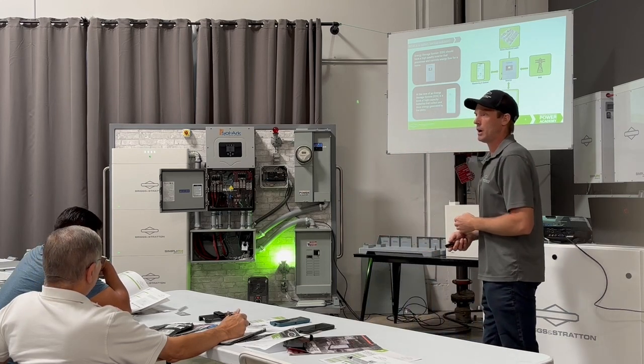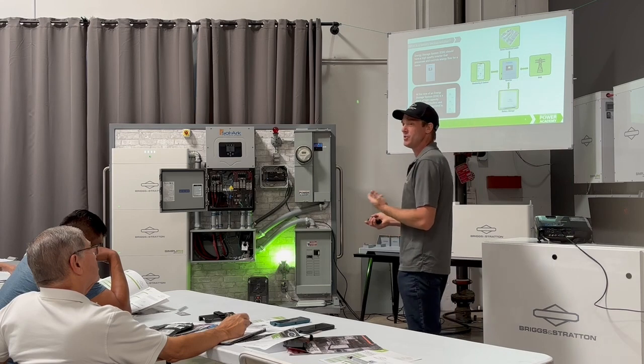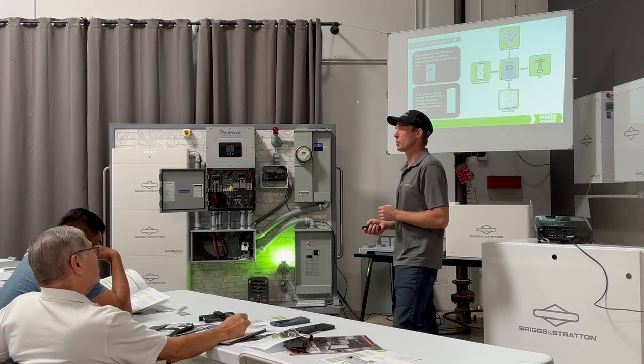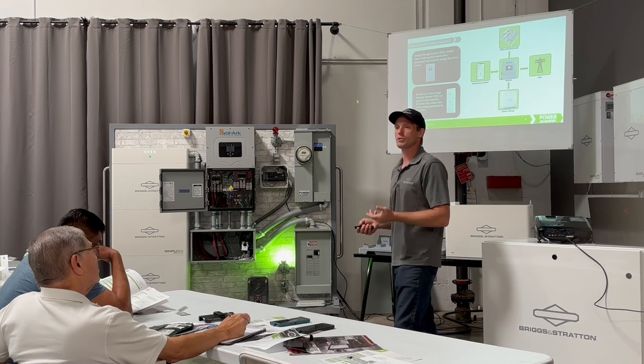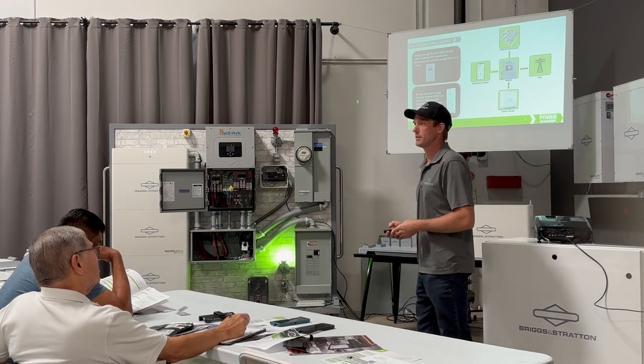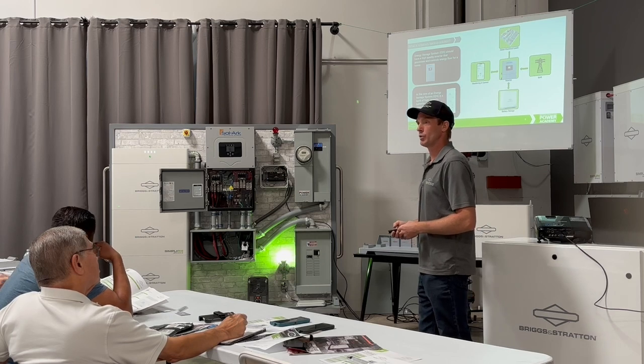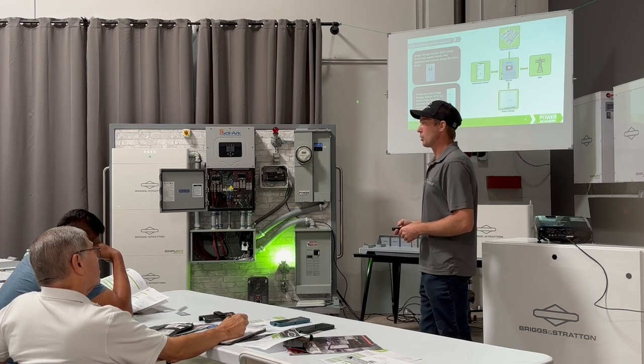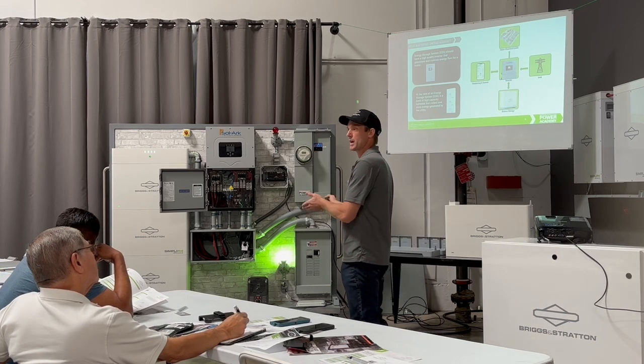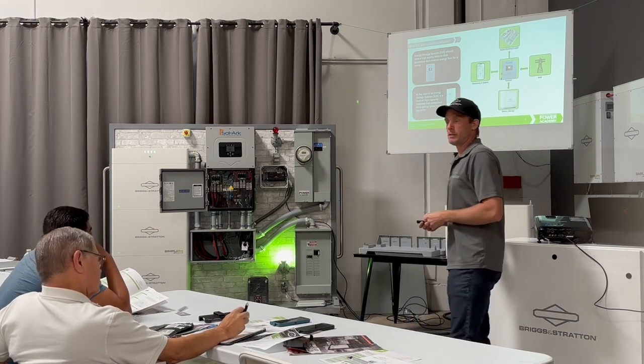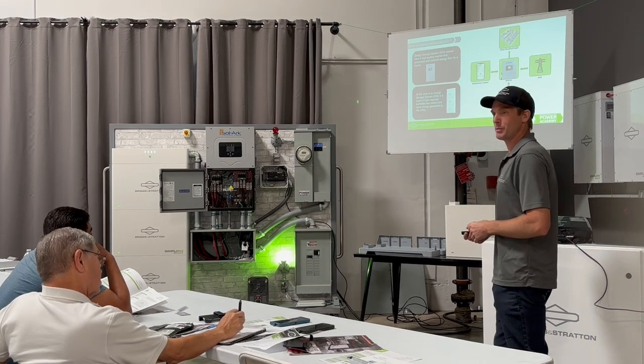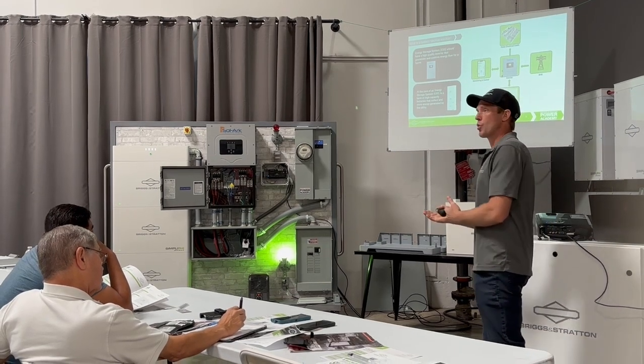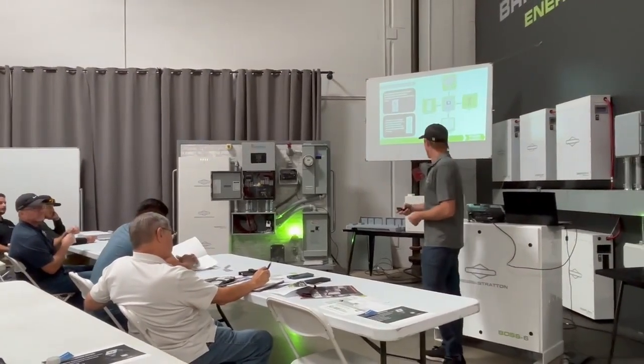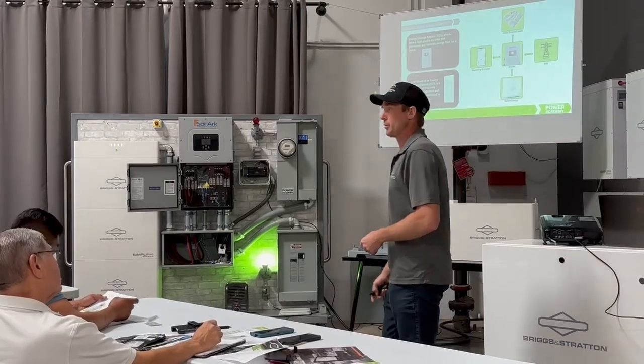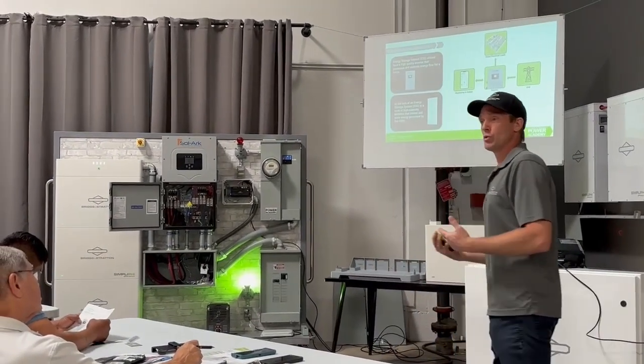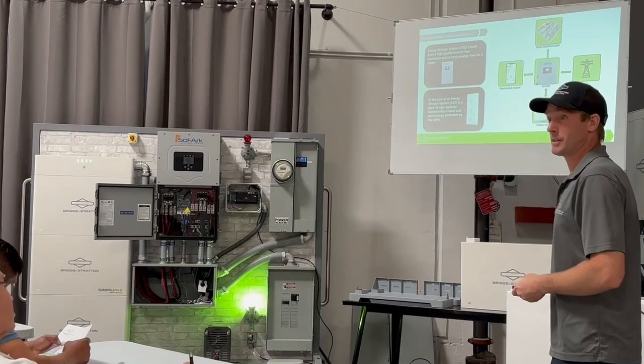I'm going to get into that, it's the longest lasting. Ten years ago, battery backup was just starting to emerge as a viable option. Batteries 20 or 15 years ago were most often deep cycle lead acid, and you'd get 5 years out of your battery bank, and it was questionable whether it was a good investment. Now we're looking at 5,000-6,000 cycles out of a battery, a 20-year lifetime. It makes a lot more sense than installing a battery system that only lasts 5 years like it used to. Now you get a 10-year warranty with unlimited cycles. These batteries, we give a 15-year warranty, unlimited number of cycles. So you're really getting a battery that lasts long enough to pay itself off.